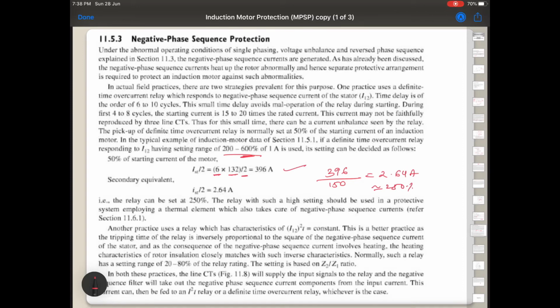Now another characteristic is I square T. I2 is nothing but the negative phase sequence current, and I square T is a constant, and this is best practice because we already have a relay with inverse time characteristics. Current versus time is inverse, so here also the current is square in nature and they match, and since it matches, here the setting is from 20 to 80% of the relay. And in both these strategies, the input signal which has the negative phase sequence current is filtered out and then given to these two strategy relays, that is I square T and definite time over current relay.